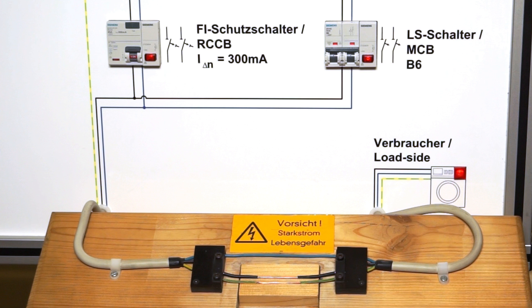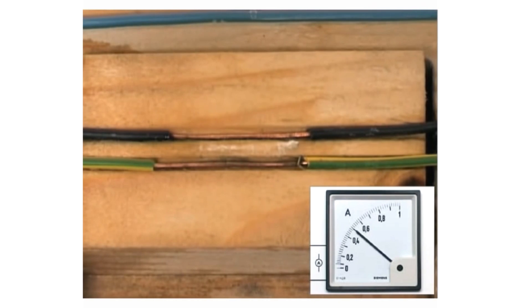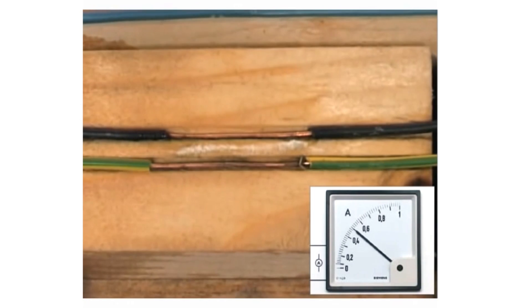The second test clearly shows why residual current operated circuit breakers are so important. A fire can start when the current flowing at the fault location is just 300 milliampere or so.